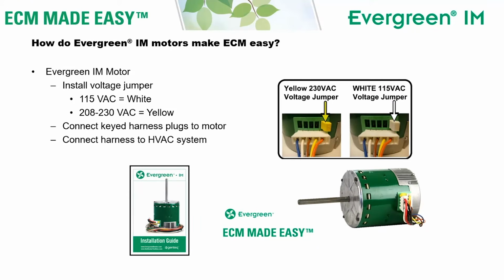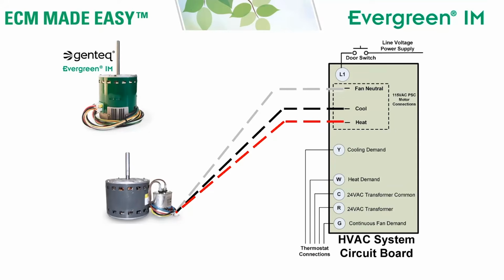The Evergreen IM motor is also very easy to connect as far as the electrical connections are concerned. Being a dual voltage motor, before you connect the wiring harnesses, you're going to install either the yellow or the white jumper. That's going to designate the motor as the voltage you want to operate it at. If you want to operate it at 208, 230, you would use the yellow jumper. If you want to operate it at 115 volts, you would use the white jumper. Then you're going to connect the keyed harness plugs to the motor and use the other end of those harnesses to connect to the HVAC system.